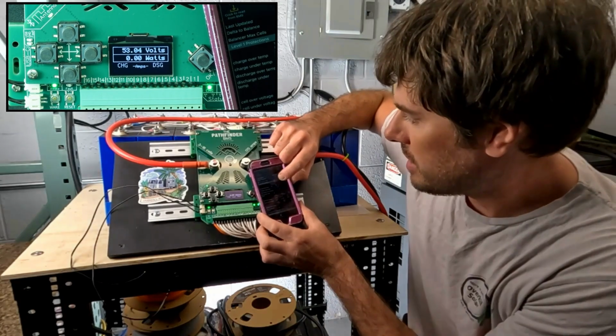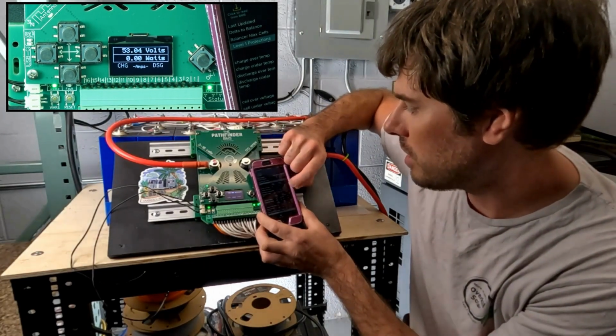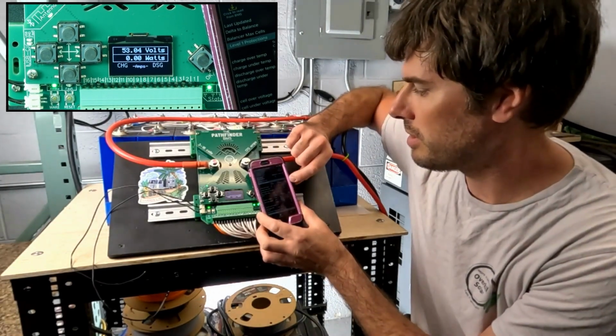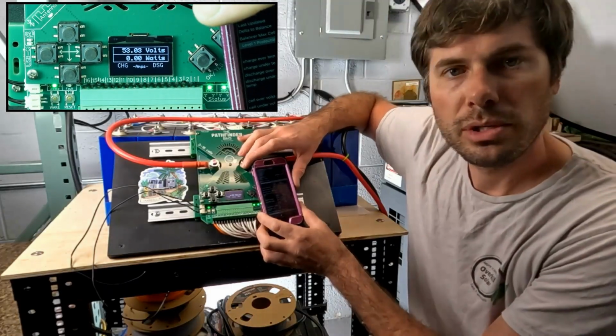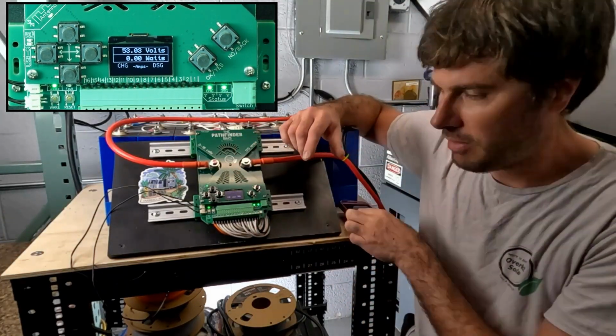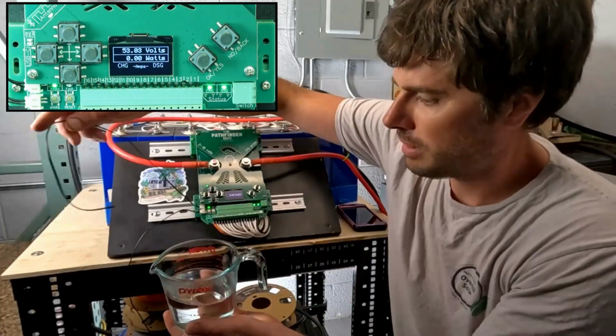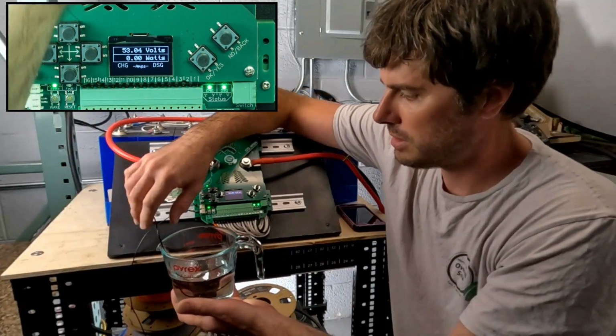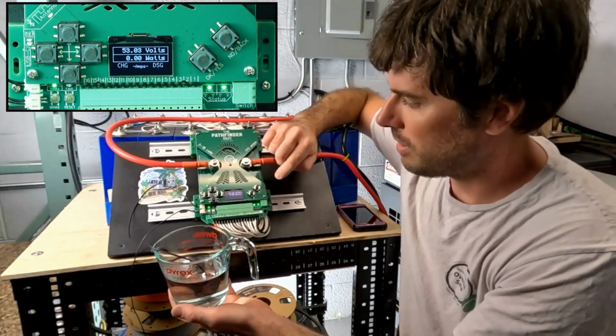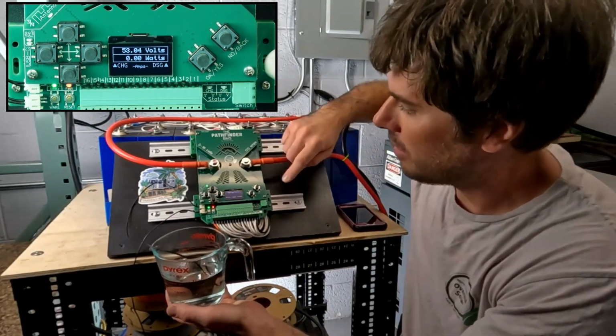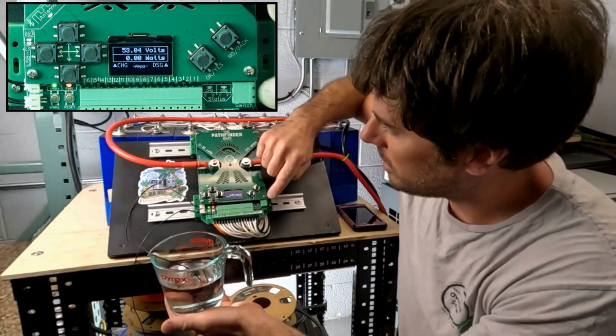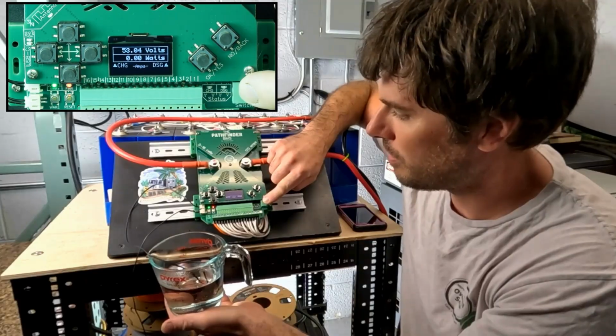Charge over temp is set to 55 C and discharge over temp is set to 60 C, both of those with a 2-second delay. So we should be able to test both of those with a cup of hot water. And we'll test probe number 1 at high temperature, and we should see both of them turn off. Okay, so after the fault triggered, we saw charge and discharge both shut off.